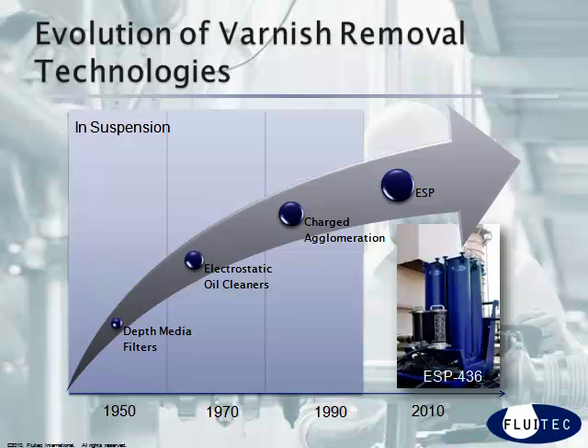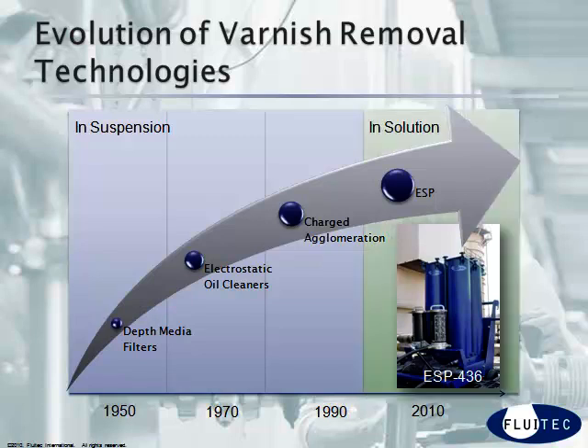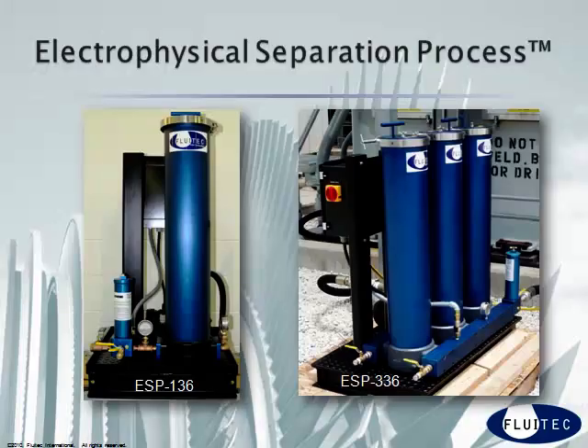Electrophysical separation process, or ESP, was specifically designed to remove soft contaminants while they are both in suspension and in solution. As a result, the technology has the ability to clean up heavily varnished lubricant systems much faster than other technologies. Most systems can be cleaned up in about a week. ESP will remove the contaminants before they have a chance to come out of solution and form deposits. It allows you to be predictive rather than reactive.